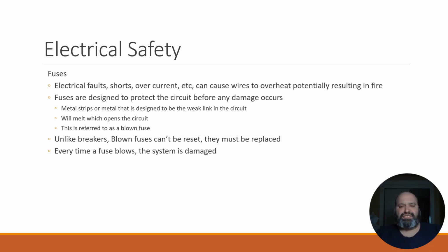Usually it's some kind of low voltage short. It could be a power surge, it could be a grounded motor, but either way, the fuse is not blowing because it wore out. Fuses don't wear out. They're designed to blow when there is something wrong. So they indicate a problem; they are not typically, in and of themselves, the problem. Unlike breakers, fuses can't be reset. They have to be replaced. And this was kind of my point: if you have a succession of blown fuses, eventually, just like multiple blows to the head, those tiny injuries will add up.